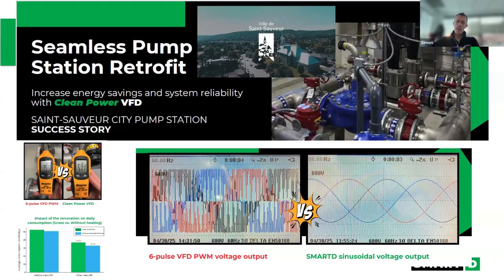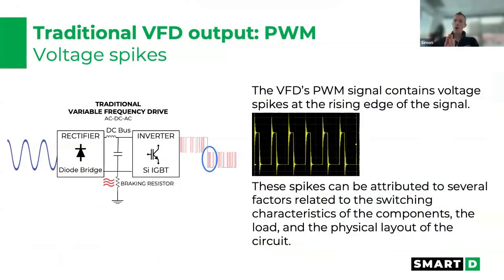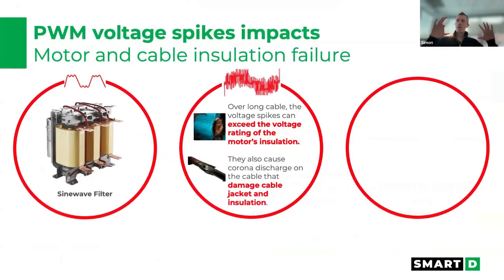Now, that's the first item that comes from the PWM, harmonics. Let's look at the next one, which is voltage spikes. On each pulse coming out of the VFD, you have a spike at the rising edge of the signal. And this problem actually increases as you have a longer cable, as I'm sure all of you know. And you have a reflected wave impact, where a wave hitting the motor gets reflected back and can be combined with an incoming wave. And so you can have your spikes, not only the small spike at every leading edge, but it can get amplified. And the longer the cable, the bigger the problem.